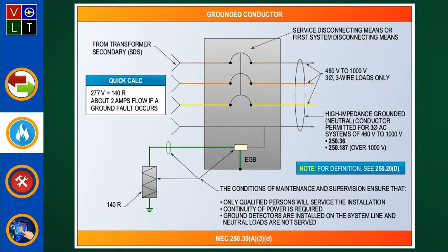And that's why I'm saying - I'd say it's common in America, but it depends on the facility. I've seen some facilities go with brown, orange, and purple. The only thing the code limits is the neutral conductor and the equipment grounds.